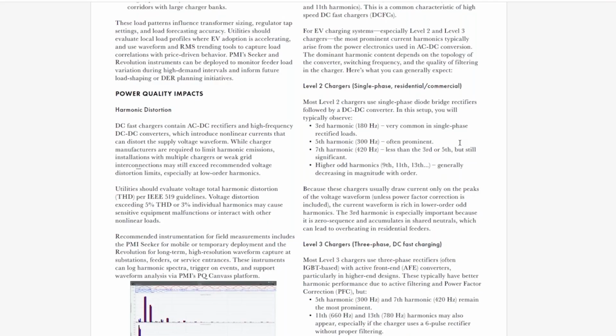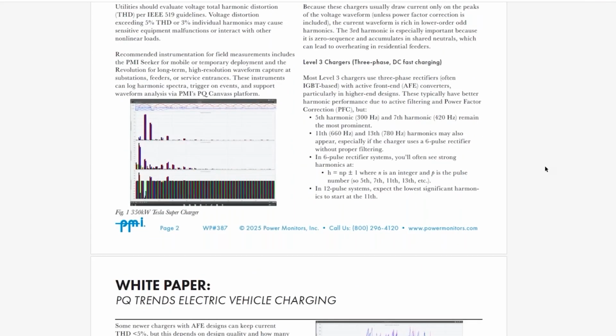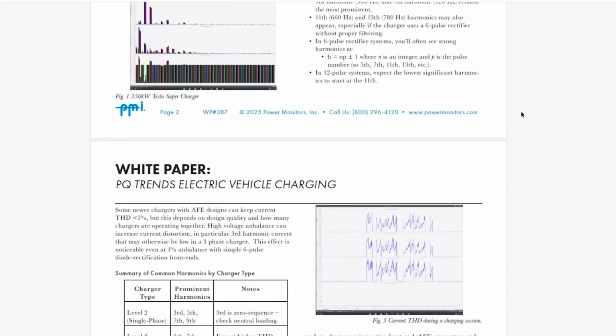But with intelligent phased chargers, spread out charging with rate structures that encourage that can help level the load so that that doesn't put too much peak load on the grid. It's when we get into these fast chargers that we get into the more interesting power quality issues. So where these are very high loads and have a fair amount of harmonics. So these are nonlinear loads and they're very large loads. And they also change relatively quickly as cars pull in, start charging, and then drive off. Because Caleb mentioned these are 350 kilowatt, even in some cases higher per car, and that adds up fast if you've got a lot of chargers.